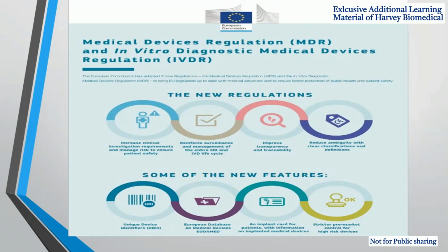So many things we use as medical devices, right? Like syringes, those are all manufactured through PVC, polyvinyl chloride. That PVC vendor was changed, and they prepared the implantable medical device, and severe deaths happened in the European Commission. Then they immediately took a call and enforced the medical device regulations. All manufacturers should follow the medical device regulations or in vitro diagnostic regulations, and any changes should be immediately notified to the notified body, and once the changes are approved, only then can they go ahead with the changes.